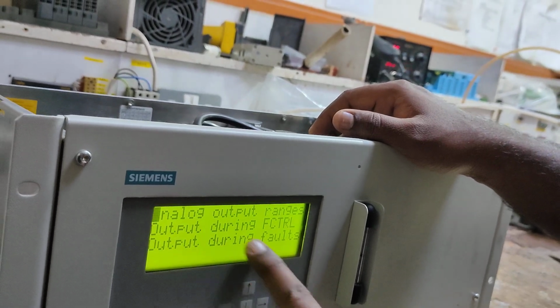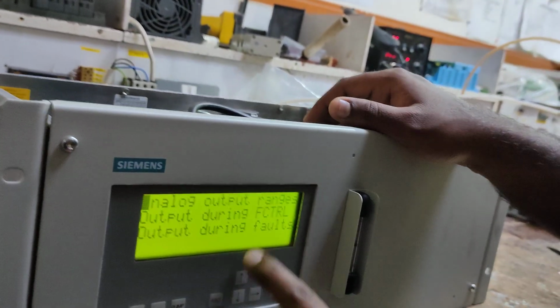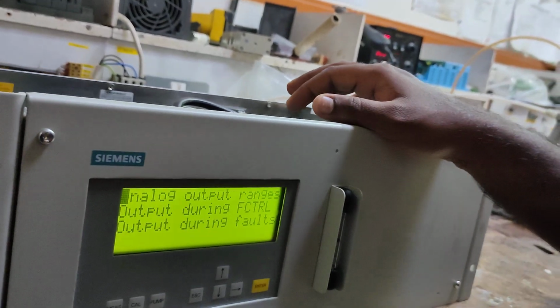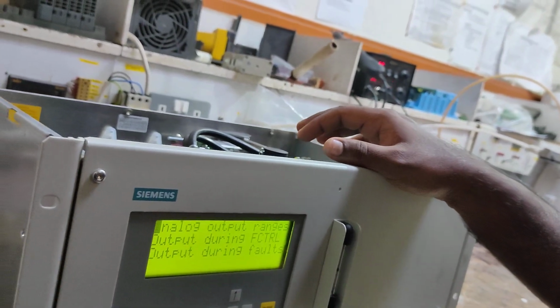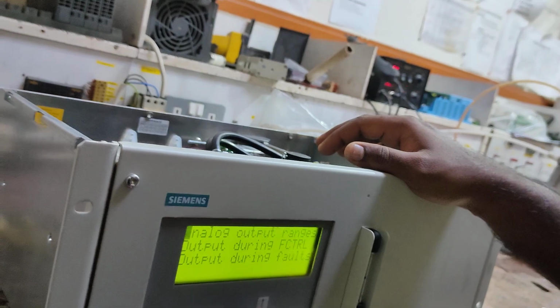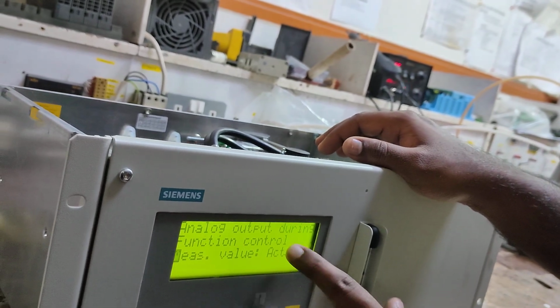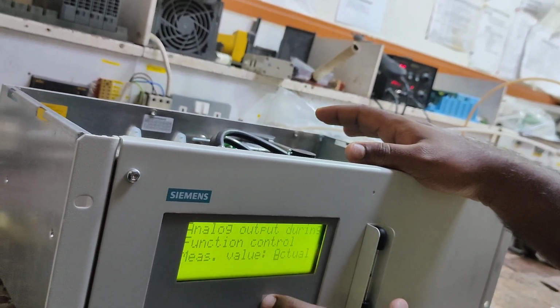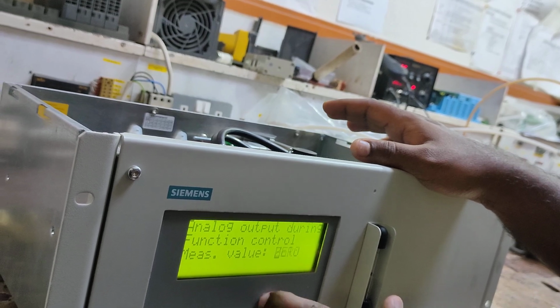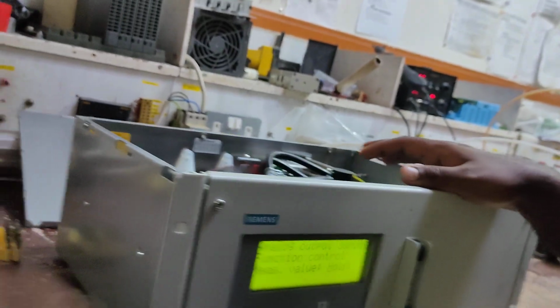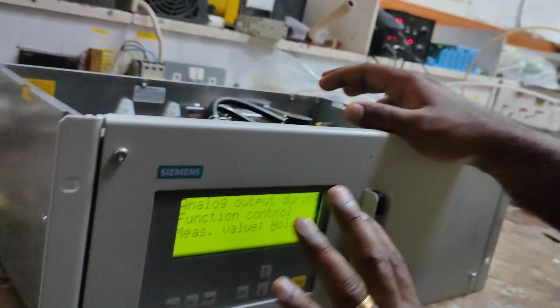Analog output, so output during function control. Function control means if you have given the passcode, then it will go into function control mode. At that time, what should the output be? Whether it should be the actual value you are measuring, 21 milliampere, 0, or hold. Hold means the last value will hold. So you have to decide on this one.